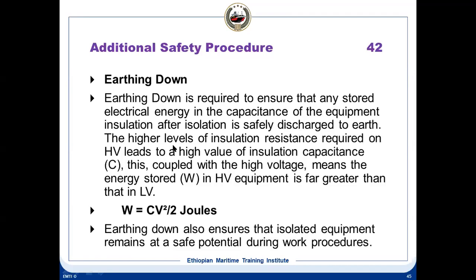residual charges. Higher levels of insulation resistance required on HV lead to high value of insulation capacitance. This, coupled with a high voltage, means that the energy stored on HV equipment is far greater than on LV. So W is the energy stored. That is, HV leads to high insulation capacitance, and W equals C V squared by 2 joules. This is the energy stored. So the energy stored will be very high in the case of high voltage.